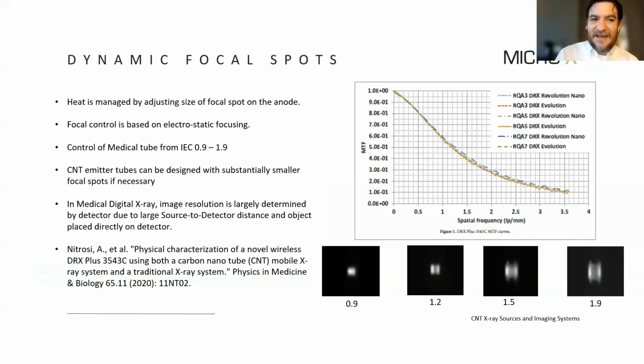The second property that our tubes have is that we can very precisely and dynamically control the focal spot on the anode. So as I mentioned before, we have a focusing cup, but we change the voltage on that focusing cup to change the electrostatics to either consolidate the electron beam or spread out the electron beam from that large area emitter. So we take that large area emitter and we focus it into the anode. And so for our medical application, we focus it from 0.9 to 1.9. And in the digital X-ray imaging application, the resolution of a digital imaging system is really determined by the detector. The source to detector distance is quite large, and the patient is on the detector, very close to the detector. So it's really the detector, not the focal spot, that determines the image quality.